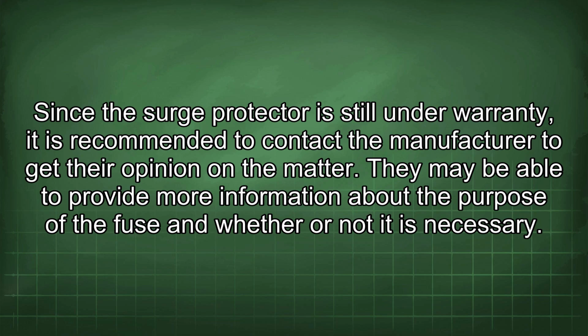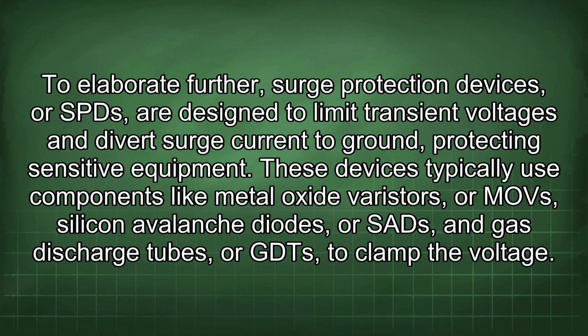it is necessary. To elaborate further, surge protection devices, or SPDs, are designed to limit transient voltages and divert surge current to ground, protecting sensitive equipment. These devices typically use components like metal oxide varistors, or MOVs, silicon avalanche diodes, or SADs, and gas discharge tubes, or GDTs, to clamp the voltage.